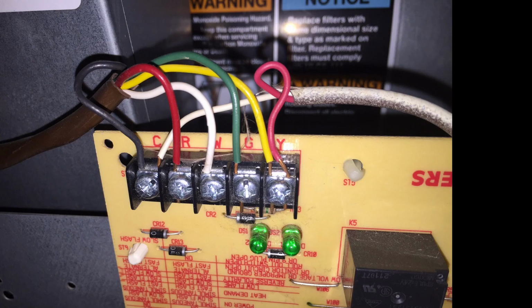Here's a close-up view of another one. And this one's, like I said, a standard hookup, okay? On the left is C for common, R for power, white for heat. You have G for your fan, yellow for your cool. But I want you to get a notification on this one. On the left-hand side, you'll see a wire feeding in, and it has 4 wires going into the control board. That's coming from your thermostat.